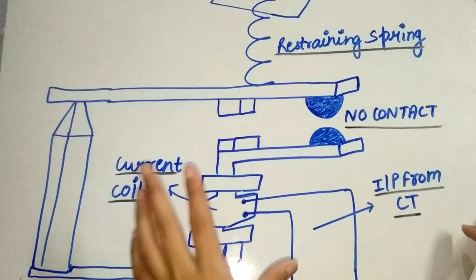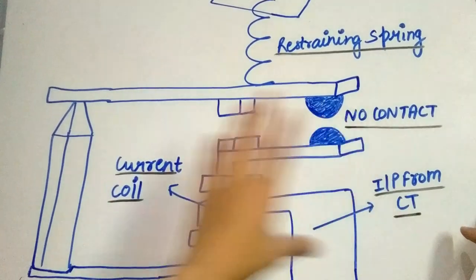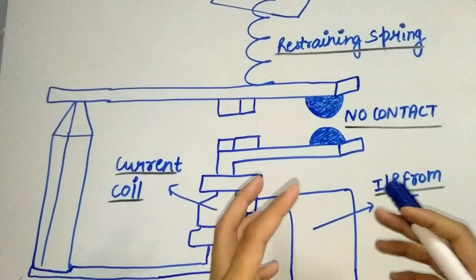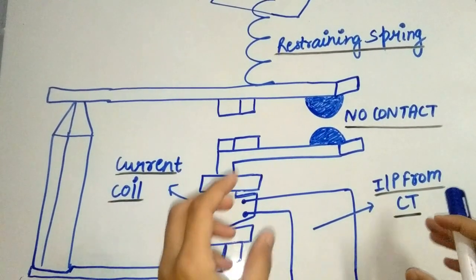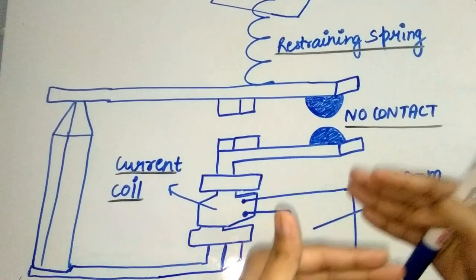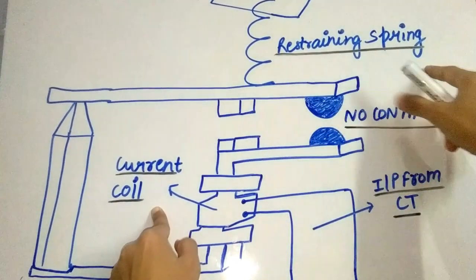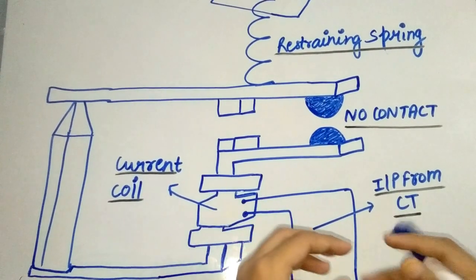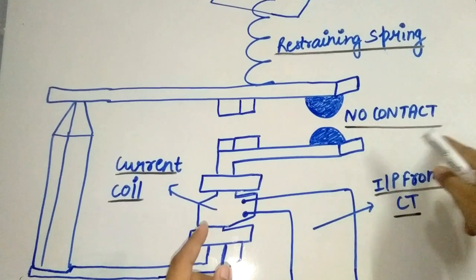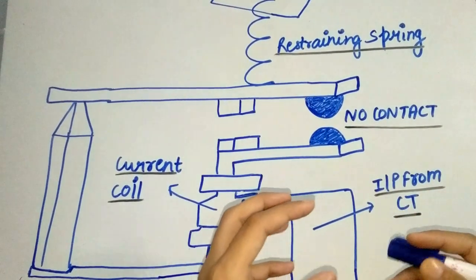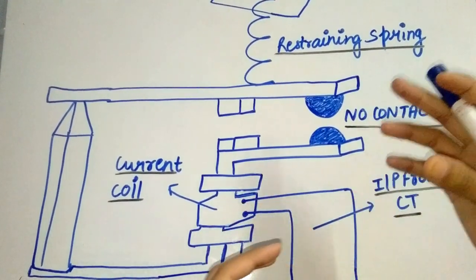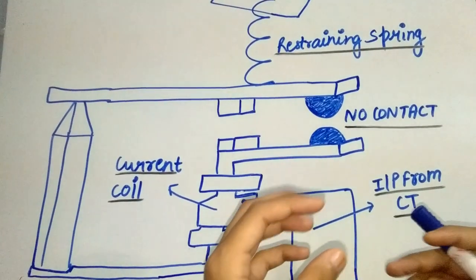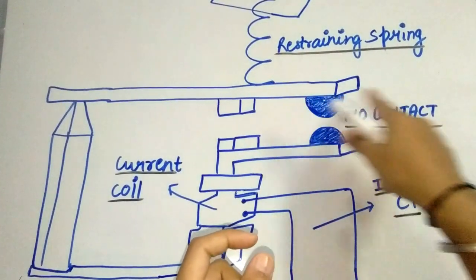First I will explain the instantaneous overcurrent relay. The construction and working principle is quite simple. There is a magnetic core wound with a current coil, a restraining spring, normally-open contacts, and input from a current transformer. When the current in the coil is not sufficient, the contacts remain open. But when the current crosses a preset value or pre-determined value, the attractive force becomes enough to pull the iron piece towards the magnetic core.